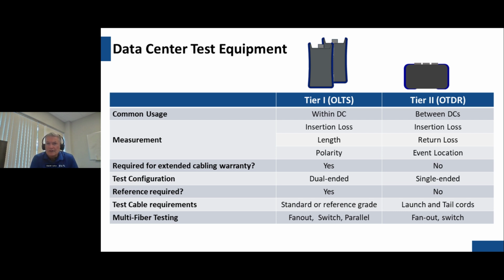So just a high-level view of the difference between these two pieces of equipment. Again, the tier one OLTS is used primarily within the data center, and this would be the tool to measure insertion loss, length of the circuit, and polarity. You'll often hear that if the end user is interested in an extended warranty, the cabling provider will absolutely require that tier one test results or certification results are provided before they'll extend that warranty. This is a dual-ended test, as we'll see in a minute—one end acts as a light source, the far end acts as the power meter, measuring the received power.